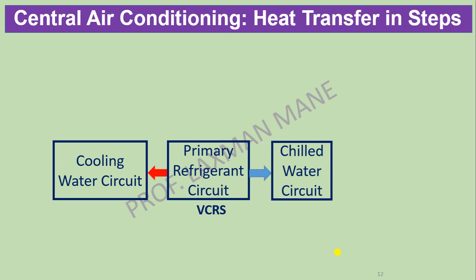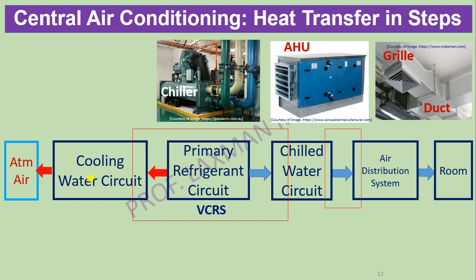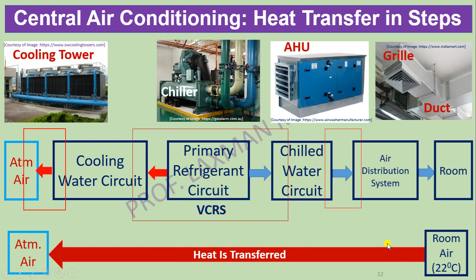The chilled water circuit produces a cooling effect by which air is cooled, and it is distributed by using the air handling unit to the different rooms by using ducts and, at the end, a grille or diffuser. Heat absorbed from the chilled water circuit by the refrigerant is rejected to the cooling water circuit. This cooling water circuit rejects heat to the atmosphere by using a device called a cooling tower. Thus, heat is transferred from the room air to the atmospheric air.